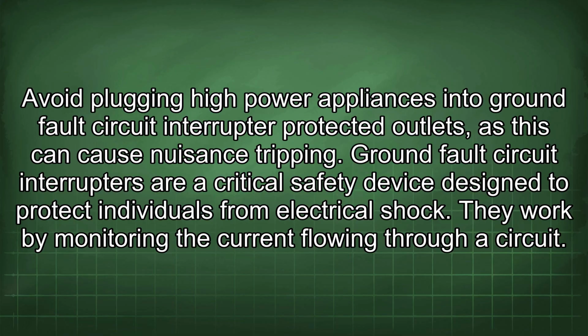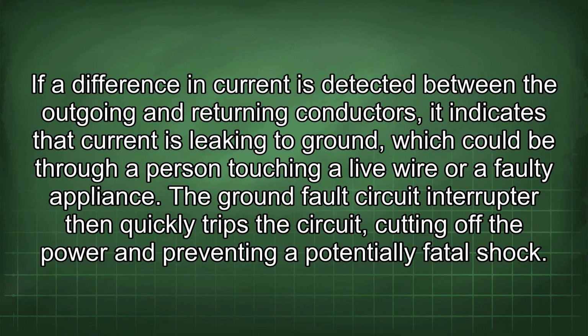Ground fault circuit interrupters are a critical safety device designed to protect individuals from electrical shock. They work by monitoring the current flowing through a circuit. If a difference in current is detected between the outgoing and returning conductors, it indicates that current is leaking to ground, which could be through a person touching a live wire or a faulty appliance. The ground fault circuit interrupter then quickly trips the circuit, cutting off the power and preventing a potentially fatal shock.